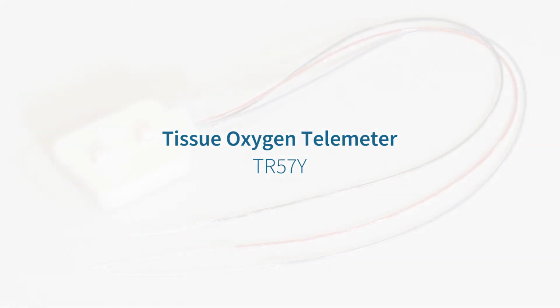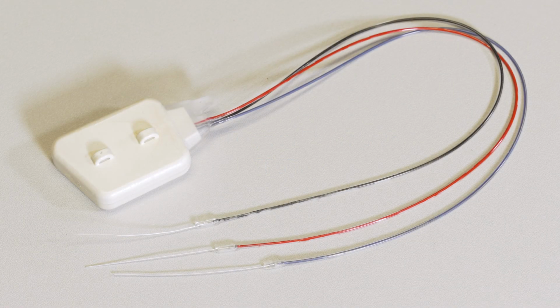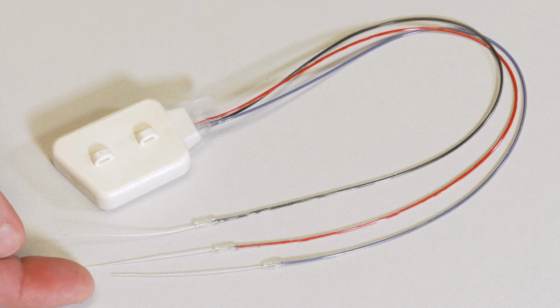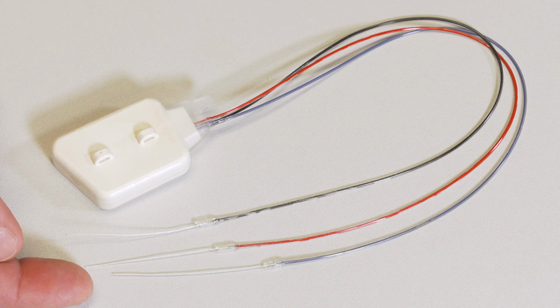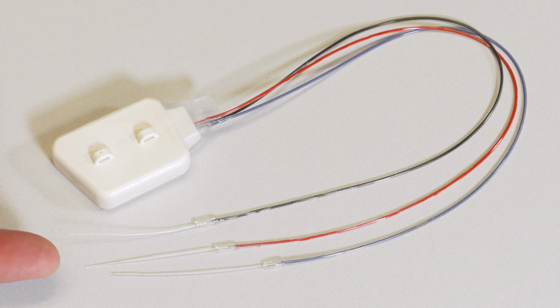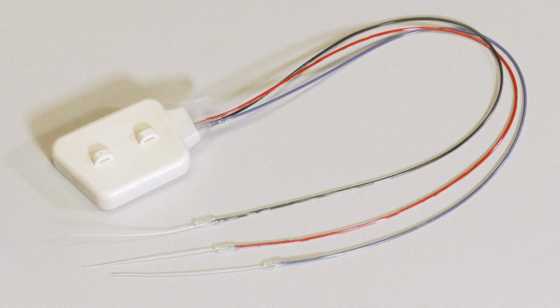This is the TR57Y tissue oxygen telemeter. It essentially acts as a potentiostat, so it applies a fixed voltage of 650 millivolts to the electrodes and measures the current response. And that current is directly proportional to the amount of oxygen in the tissue. The blue electrode has a carbon paste electrode attached, and that is placed wherever you want to record your tissue oxygen. So that might be in the kidney or in the brain, for example. The platinum silver electrodes on the red and the black electrode leads act as the reference and the auxiliary leads to complete the circuit.